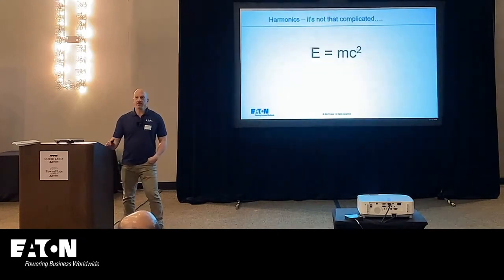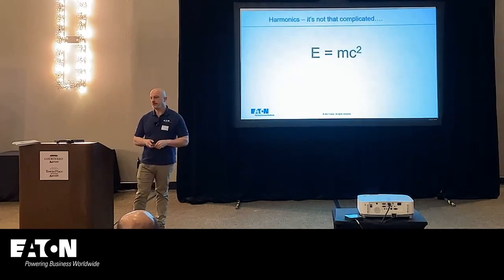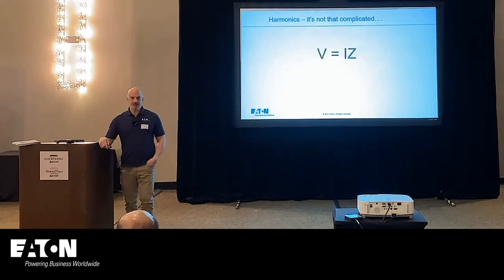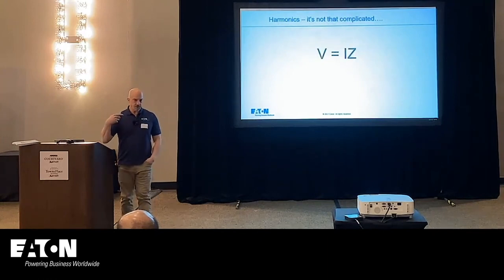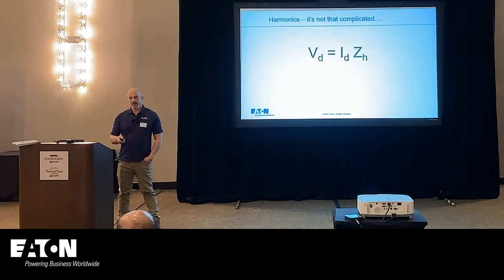But it seems really complicated, doesn't it? So everybody's always said, oh, harmonics are really complicated, we need to worry about it. It's not really that complicated. What it is, it goes back to Ohm's law. Voltage equals current times impedance, okay? And more specifically, voltage distortion equals current distortion times the harmonic impedance.